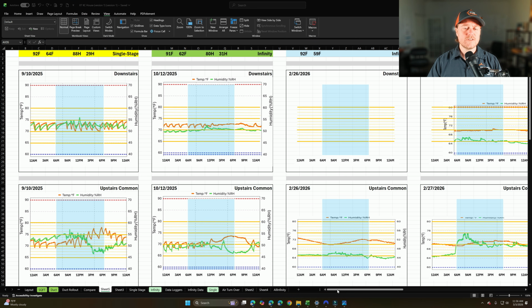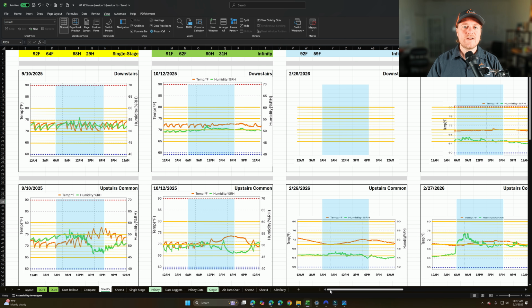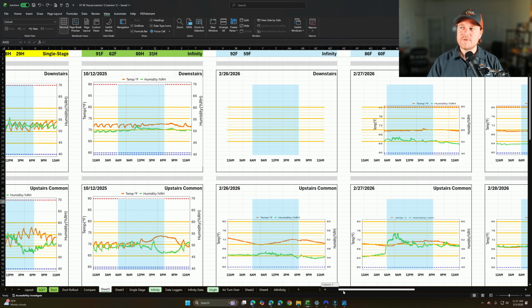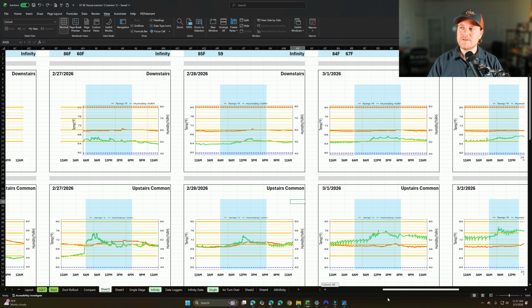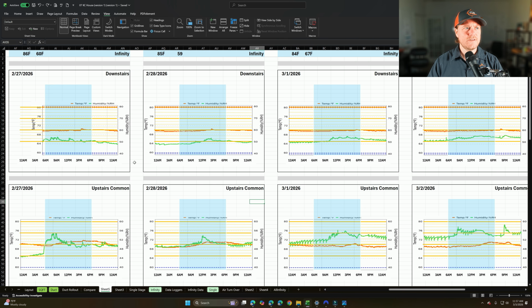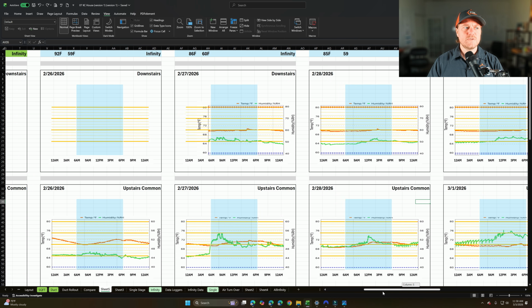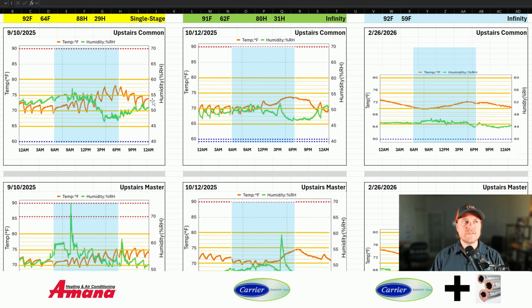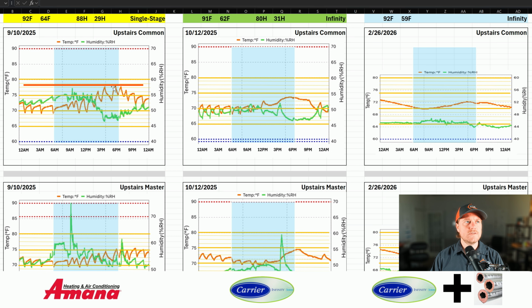With all the groundwork laid, let's go ahead and take a look at our data loggers. For the data logger at the thermostat, I'm not going to spend too much time on it because there's really not all that much to see here. The temperature is set at 70 degrees and the data logger is showing that it's just staying at 70 degrees. Let's jump over to the upstairs common area. On the single stage system, you can see that temperatures were getting all the way up to around 77, 78 degrees. After replacing the equipment, you can see that we were able to maintain temperatures under 74 degrees. And after we replaced the ductwork, you can see that came down to around 72 degrees, or 2 degrees above what the thermostat temperature was set at.